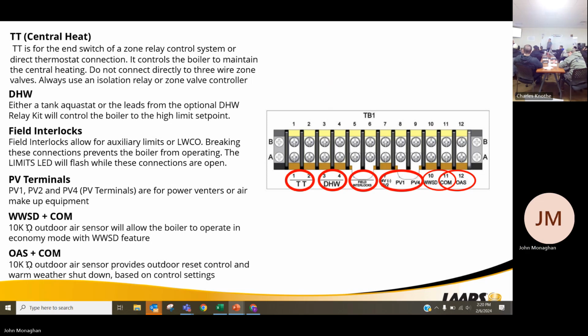Field interlocks. What do you guys need in your installed systems today here in New York? What else? High limit. That's where you're going to win them. Okay, your field interlocks. And then John's point, 7, 8, 9 are your other ones. And outdoor sensing. If you use outdoor sensing, that would be your last concern. And the control that we're using, our low water cutoff can be auto reset, manual reset, or can be turned off. So you can have your manual reset low water cutoff inside the unit. But I don't think here in New York they allow that, right? They want that at the higher point above the heat exchanger, is that correct? The water cutoff here in New York.